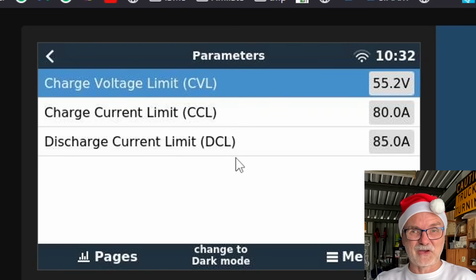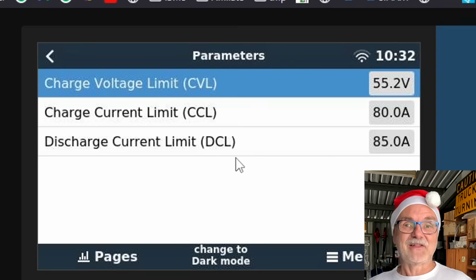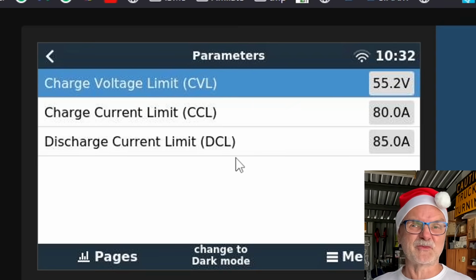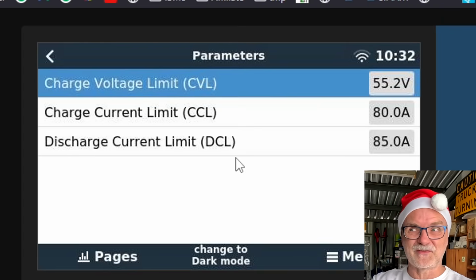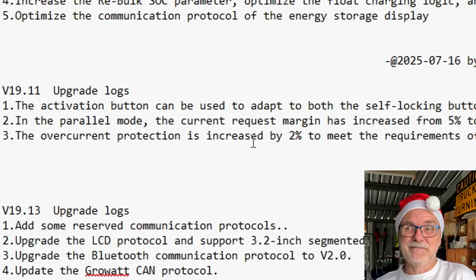This is again the physical boundary before the BMS turns off your battery, disconnects the MOSFETs, but it tells the inverter, hey, you can only discharge me with 85 amps. Even here, a bit of a margin if you start a pump or have a surge or something. So I don't know exactly what they mean by increase by 2%, because we now have 15% less what is reported to the inverter.